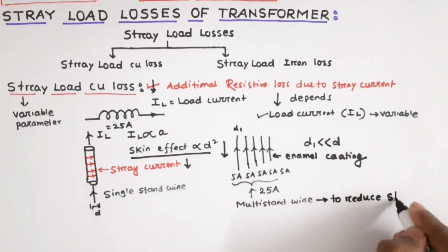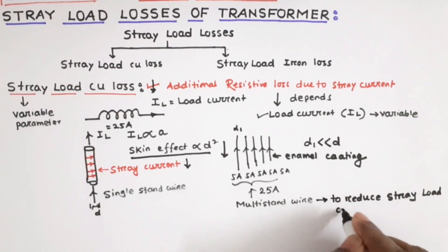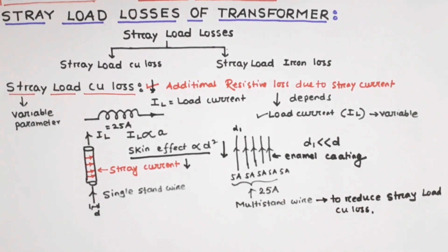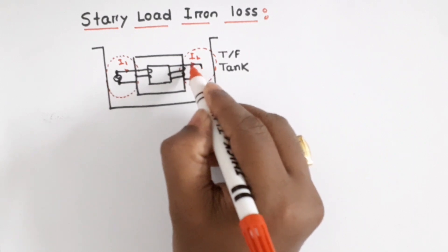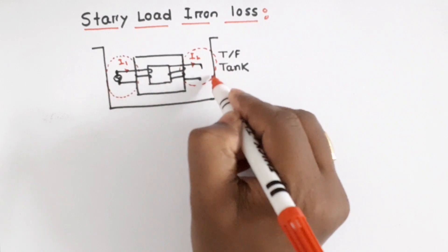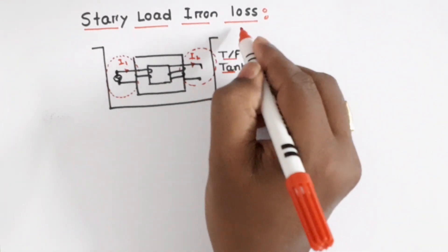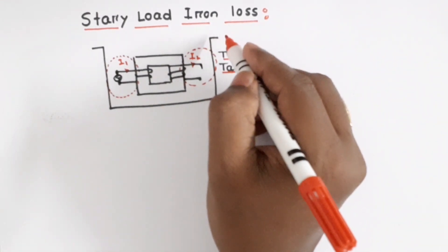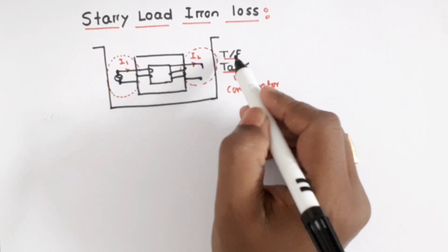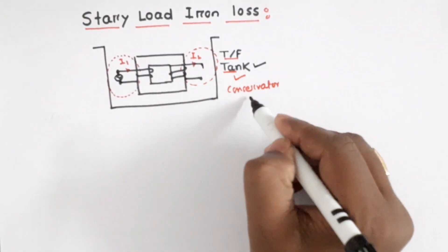Now let us start with stray load iron loss. Whenever current is flowing through the transformer winding, a leakage flux will be produced. Some of this leakage flux will link with the transformer tank, transformer conservator, and other parts. The losses in these different auxiliary parts — like the transformer tank and conservator — due to this leakage flux are called stray load iron loss.